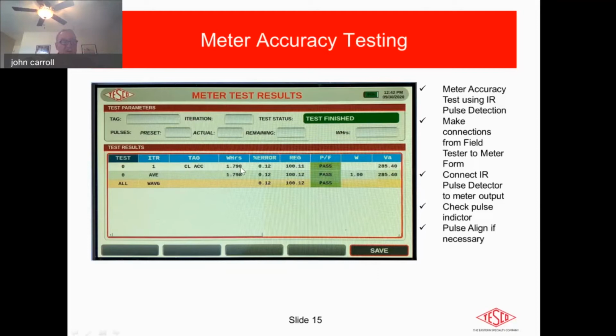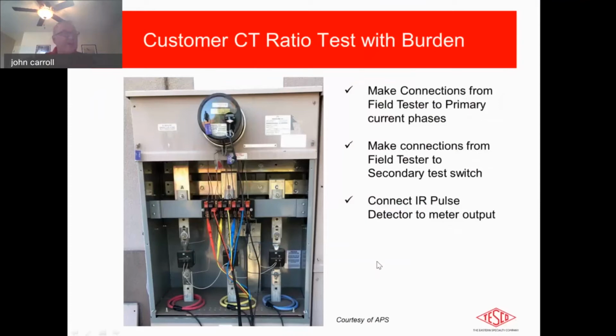It's telling us we have 1.798 watt hours. We set it up to read 1.8 for one pulse. So that's our accuracy test. The error is very small. The registration is 100.11 and it's passed. The other two rows underneath are just the average weighted and an average. You can see the two indications there. But essentially, that first point there is a pass condition. If you're satisfied with that, you can just hit save and save the results. The other grayed out screens here will be filled in with options to maybe redo the test. But if you're happy with that, you hit save. And so that's really a customer load test from a meter standpoint.